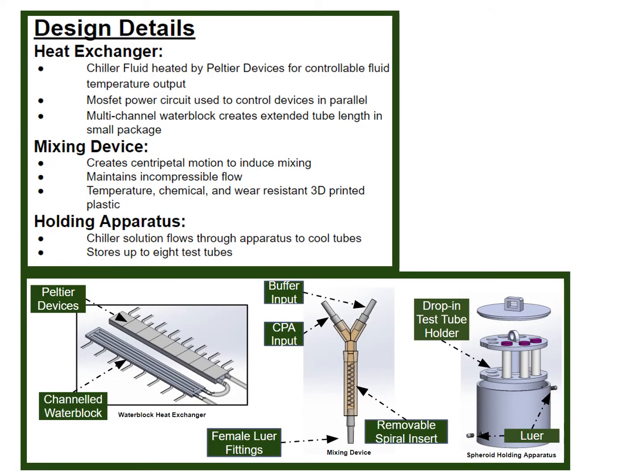Here are the design details for each subsystem. For the heat exchanger, the chiller fluid is heated by Peltier devices, which control the output fluid temperature. A MOSFET power circuit in parallel is used to control these devices, and multi-channel water blocks create the required extended tube length in a small design package.